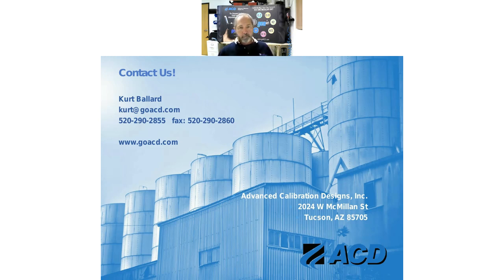From Asad Ali, do you have literature on natural gas blend for calibration? Well, right now we don't have a methane generator. Our only combustible gas is hydrogen. And the way our systems work, we make up to a 500 parts per million hydrogen generator. But for natural gas methane, you're looking at 2.5% by volume for a 50% LEL mix. So right now, we don't have anything in that high of a range. Okay.